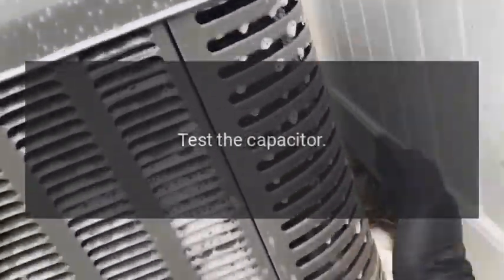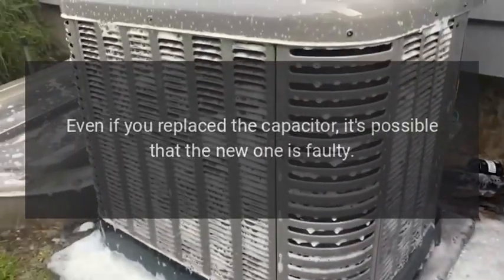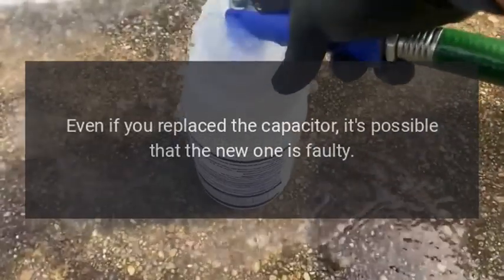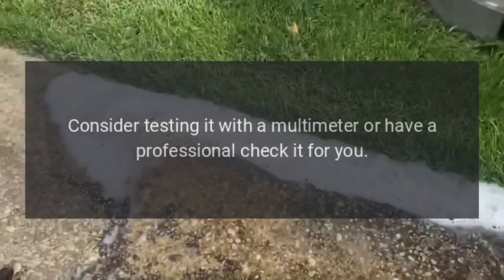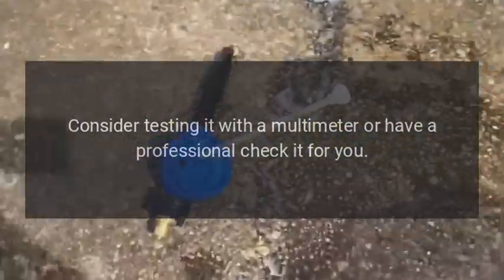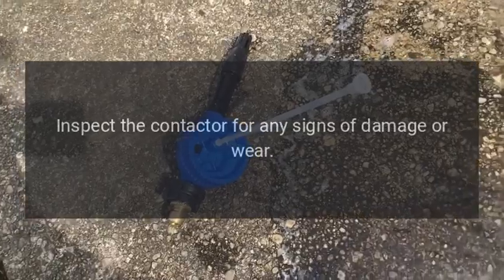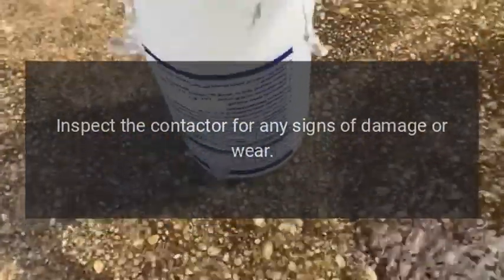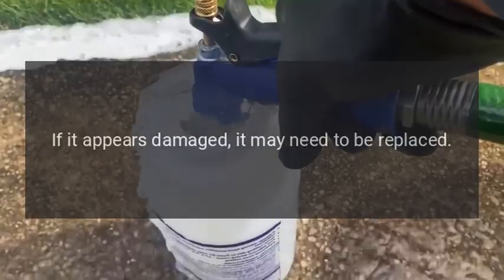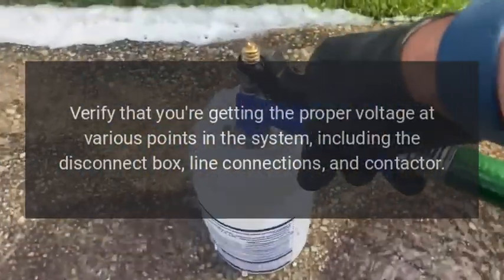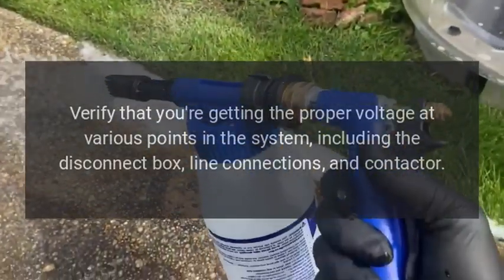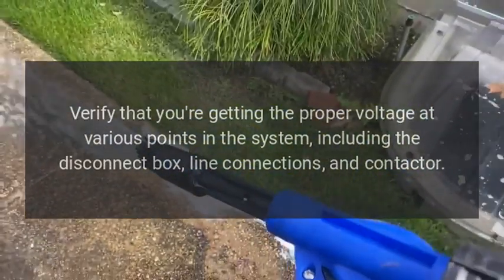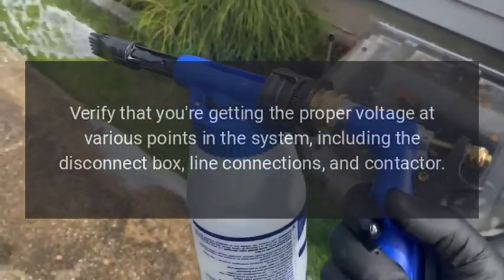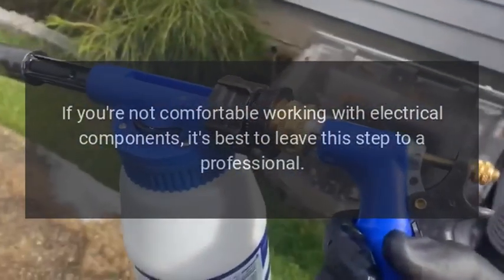Test the capacitor. Even if you replaced the capacitor, it's possible that the new one is faulty. Consider testing it with a multimeter or have a professional check it for you. Check the contactor. Inspect the contactor for any signs of damage or wear. If it appears damaged, it may need to be replaced. Check for voltage. Verify that you're getting the proper voltage at various points in the system, including the disconnect box, line connections, and contactor. If you're not comfortable working with electrical components, it's best to leave this step to a professional.